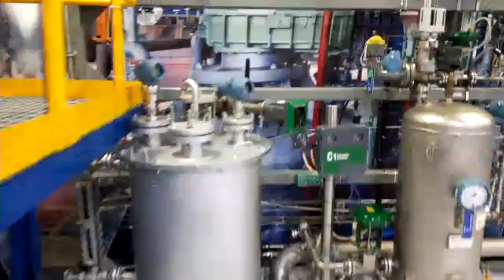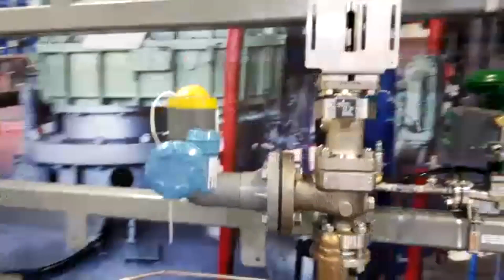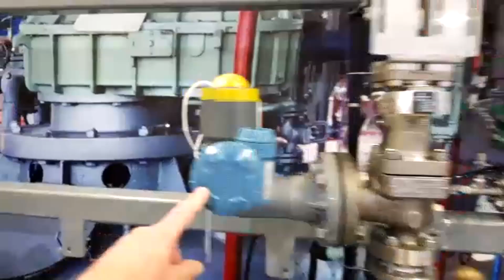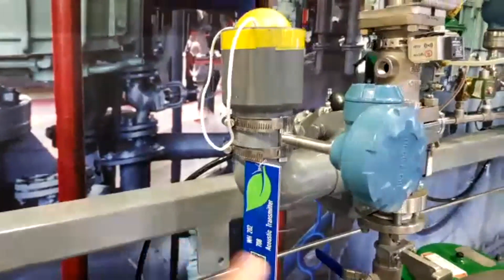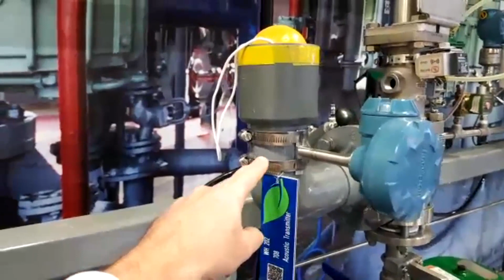Now, the next thing I wanted to show you is a PRV, pressure relief valve, a very important safety device. It's also been fitted with an acoustic sensor, wireless, the same sensor as on the steam trap. Again, this one is non-intrusive — it simply clamps onto the outside of the pipe. No cutting, no drilling, no welding. So you can install these sensors on your relief valves and steam traps today, no need to wait for a shutdown.